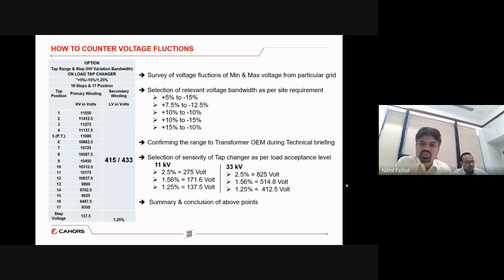We have to see whether it falls into option 1, 2, 3, 4, 5, whether it is +5 -15, +10 -10, +15 -10, and so on. Then it is to be confirmed to the transformer manufacturer who is sharing the offer, so that it can be taken into account at the design and offering stage. Otherwise, when the transformer is delivered, many people call and say that our transformer tap changer is stuck at one position and not moving ahead. That means the tap range is not appropriate. So that is the homework we have to do.